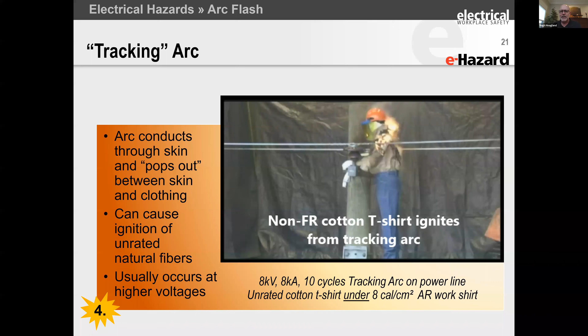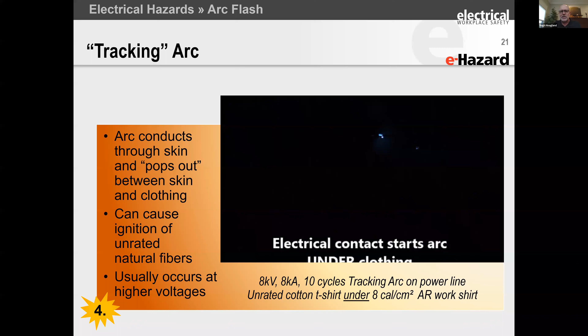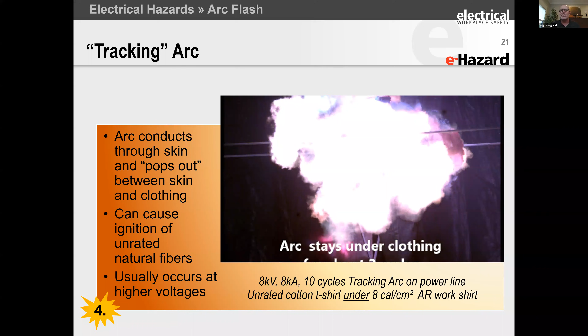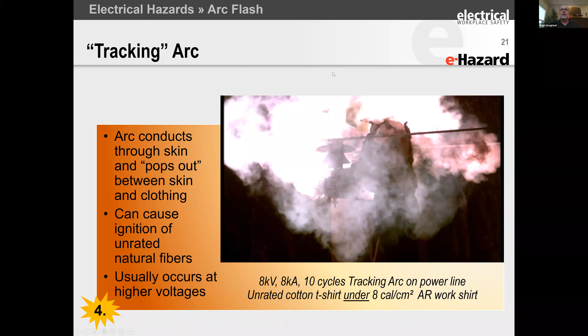So the arc in a box, all the energy is focused because the piece of equipment is focusing it. Then this is an overhead line type arc, and this was an accident replication. This person's flame resistant shirt had a couple of holes in it. It was completely scorched underneath the clothing, and the t-shirt just disintegrated, and the company was thinking that the shirt was the problem. And I said, no, it's because this person actually touched the power line, and the arc went underneath the clothing. We did this several times, and one time we blew the shirt off. It came off the person's arm and wrapped around the power line because of the energy underneath the garment.